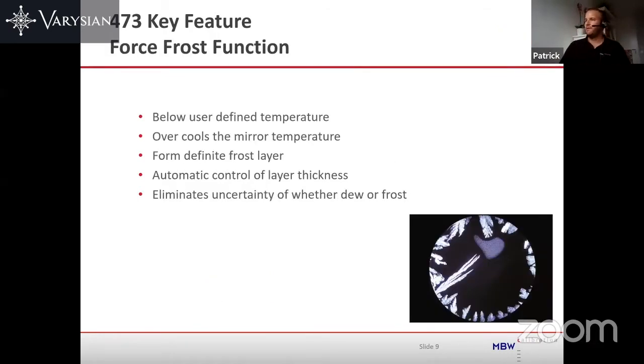A key feature of the 473: maybe some of you don't know this, but water doesn't always freeze at 0 degrees, but it always melts at 0 degrees. So to calculate a dew point or a frost point when we're at 0 degrees, the 473 has a key feature where we cool the measuring head way below 0 to force the water to freeze, and then we take the temperature back up, and we know that it always melts at 0. So that's a key feature.